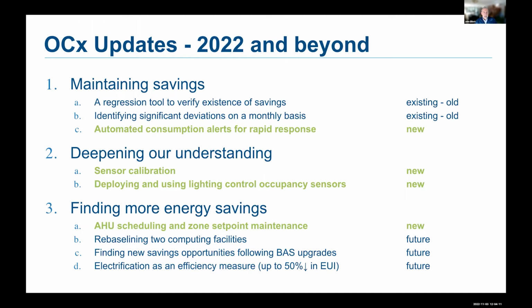We have another process in which we look at all of the meter reads that come in every month, across hundreds of electricity and gas meters. We also do a regression analysis there, comparing the monthly consumption to what we expect to see based on a regression from previous years' data. So it allows us to flag any anomalies, and then we go investigate those monthly readings. Often it can be just data quality problems, but it can also identify something that's gone wrong and is consuming a lot of energy, or some new energy use or water use that we weren't aware of, and then we can go investigate it.